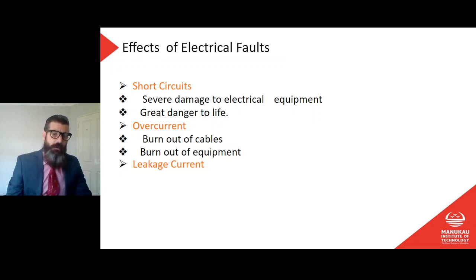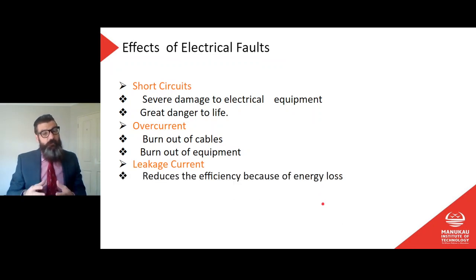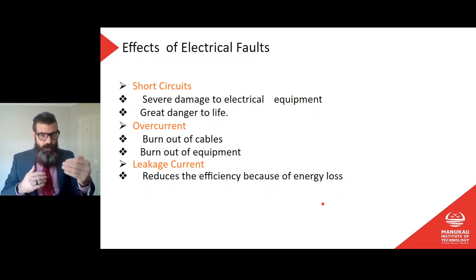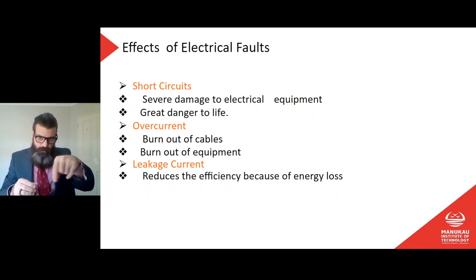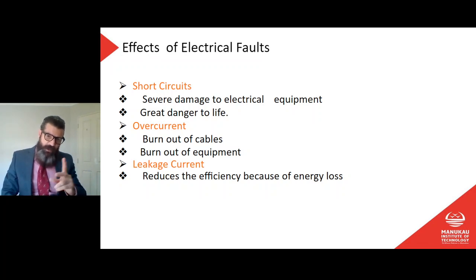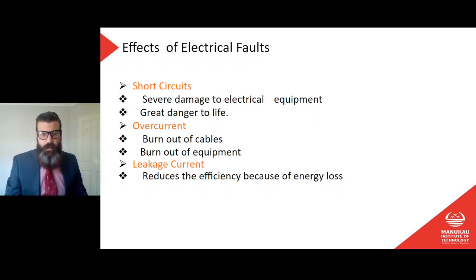or equipment. Leakage current, so this is where we get a small amount of current flowing to earth. And we use an RCD to protect us from leakage currents, right? So the effect of leakage current is that it reduces the efficiency of a circuit because of energy loss. Because instead of all of the energy going through whatever it is that we're using, some of our energy is going just down to earth. So there's just a small amount of current flowing that we get no use out of. So then we're paying for energy that we're not using.